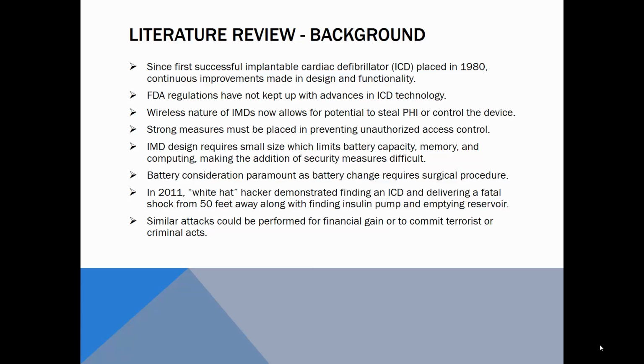In reviewing the literature, there is substantial background in IMD development and lack of security. Since the first successful implantable cardiac defibrillator, ICD, was placed in 1980, there have been continuous improvements made in design and functionality. At the same time, FDA regulations have not kept up with these advances. The wireless nature of IMDs now allows for the potential to steal protected health information or even control the device. Strong measures must be put into place in preventing unauthorized access control of these devices.